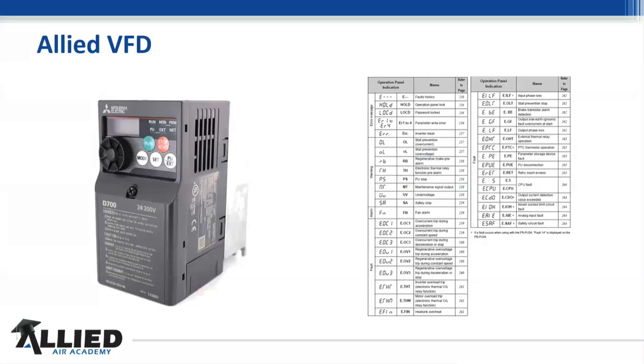There's a good example of some of the codes there. Stall prevention overload, error inverter reset. I mean, it gives you exactly what's happening with it. And 9 times out of 10, if we set and we get the right blower packages and we set everything up right, we're not going to have very many issues. Whenever I get the phone call that I'm going out on overamperage and this, that, and the other, we go over the basics first, and we usually find out the inverter's doing exactly what it's supposed to do.